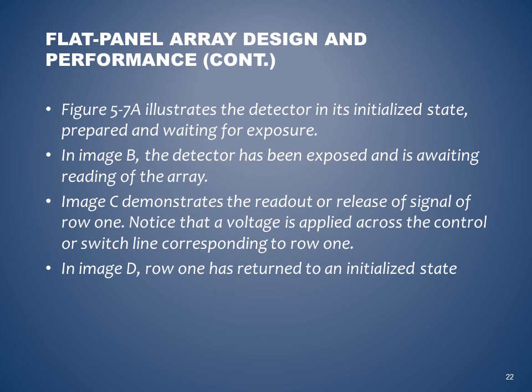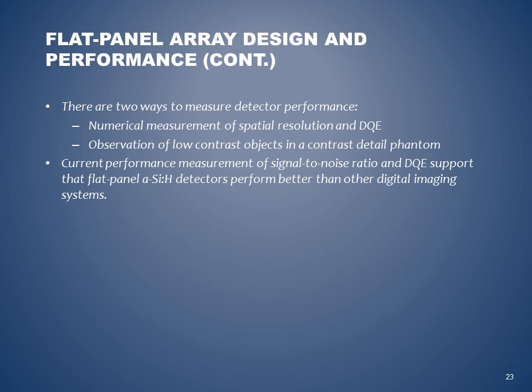Figure 5-7A illustrates the detector in the initialized state, preparing and waiting for exposure. In image B, the detector has been exposed and is waiting for reading of the array. C demonstrates the readout, or release of signal, of row 1. Notice that the voltage is applied across the control or switch line corresponding to row 1. In image D, row 1 has returned to an initialized state.